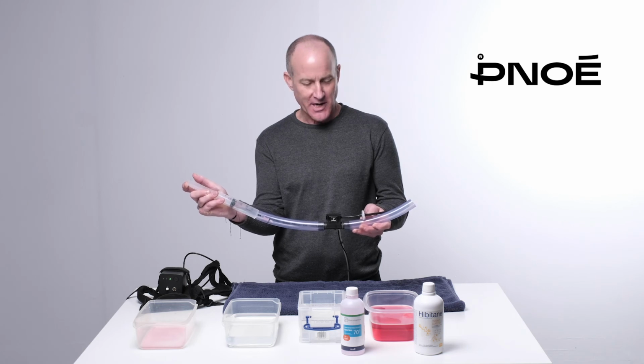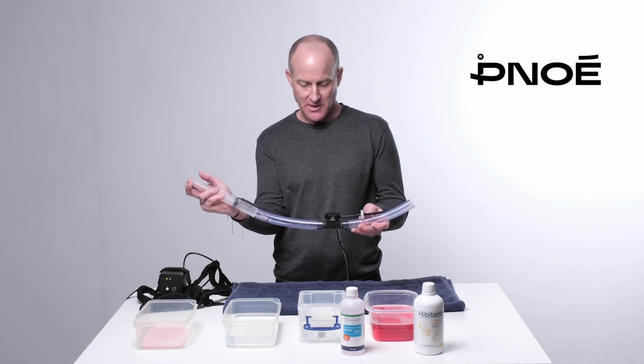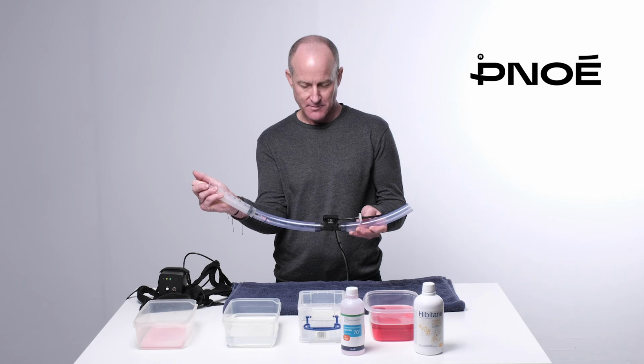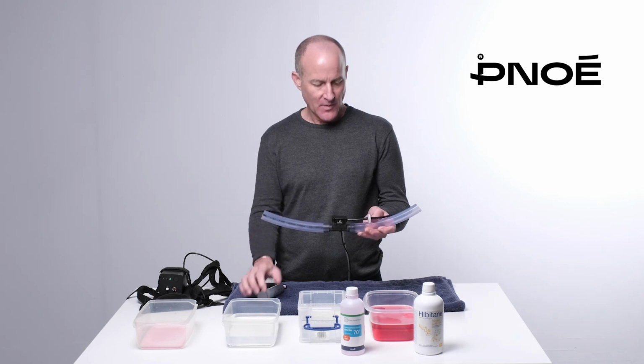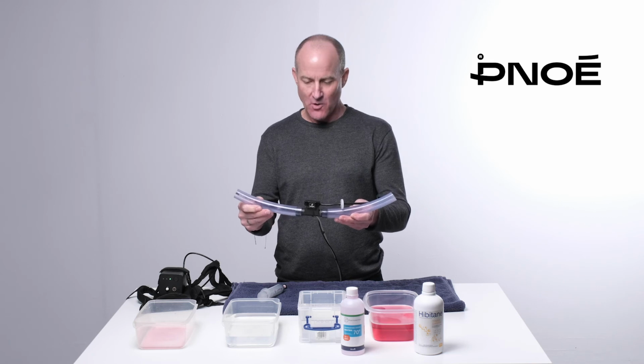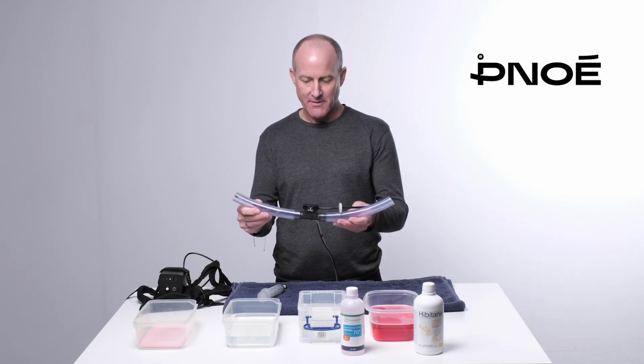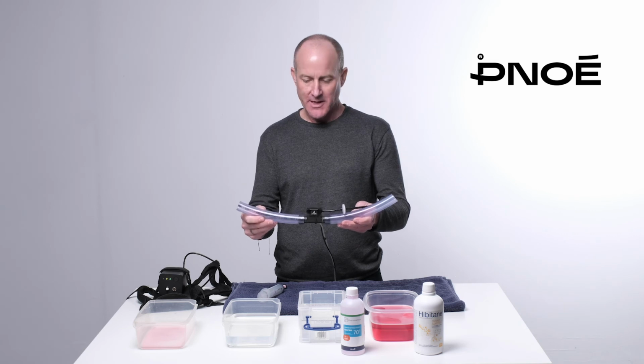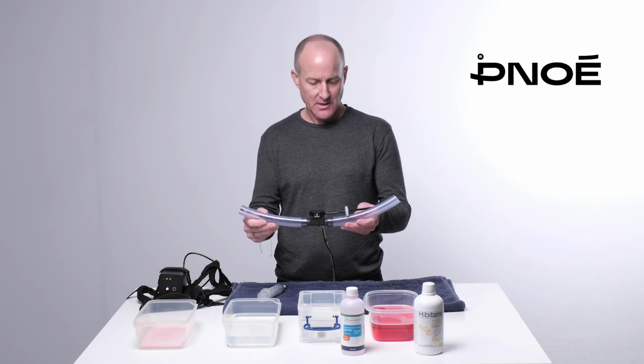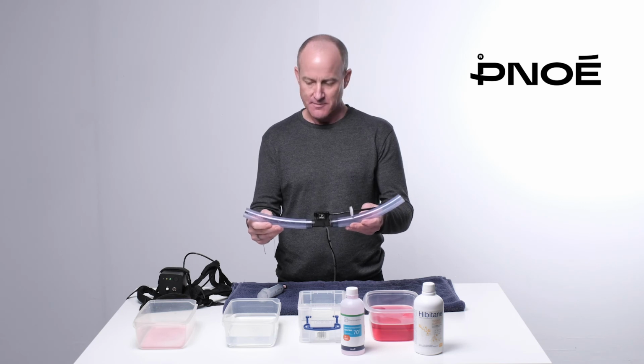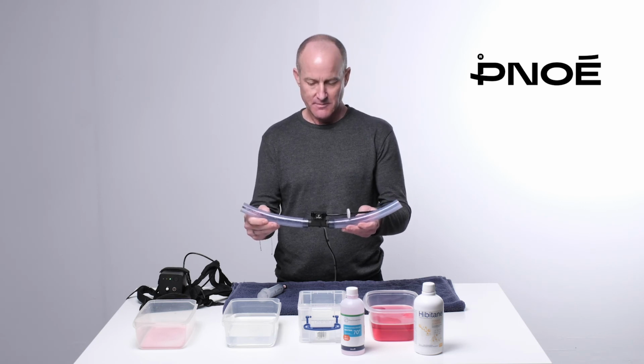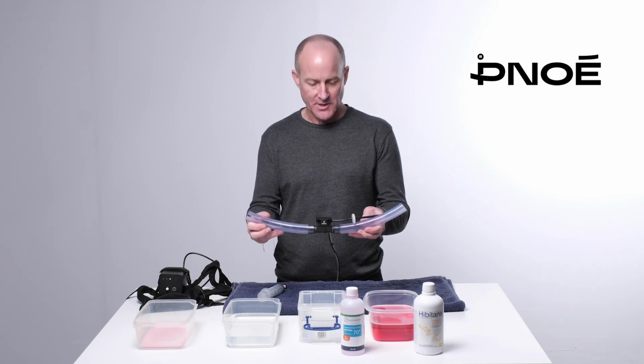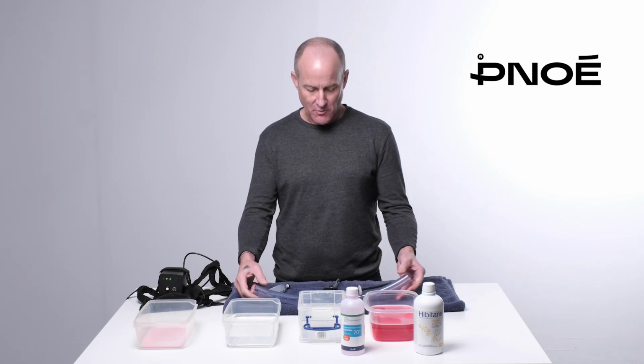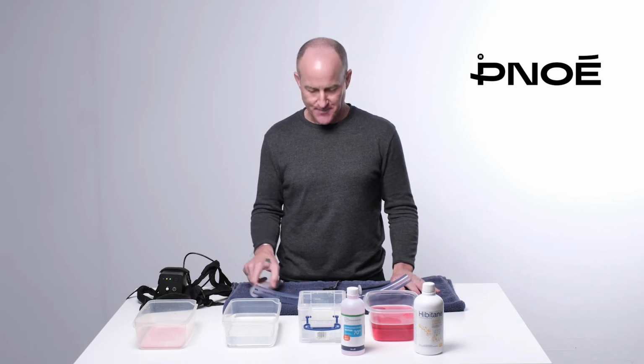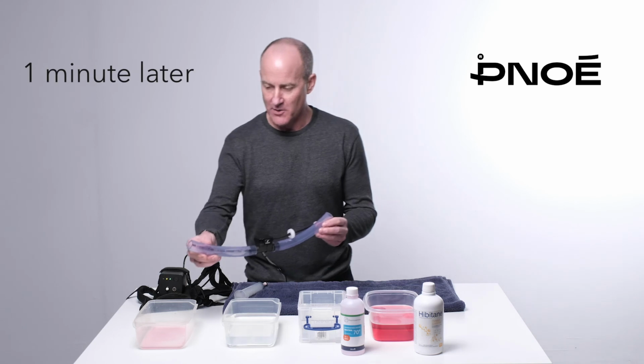And you're going to put your 70% alcohol solution in the tube. Again, rocking back and forth to make sure that it gets through all the cavities of the flow sensor. Again, 1 minute. And then after 1 minute, you're going to allow it to remain in contact for 1 more minute. You're then going to pour out that solution.